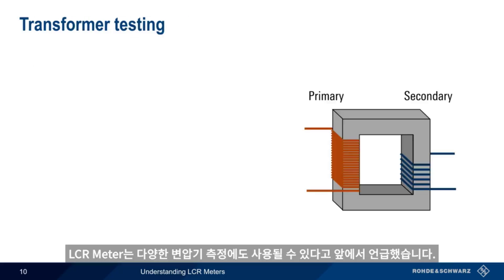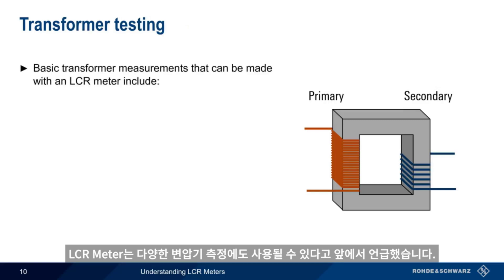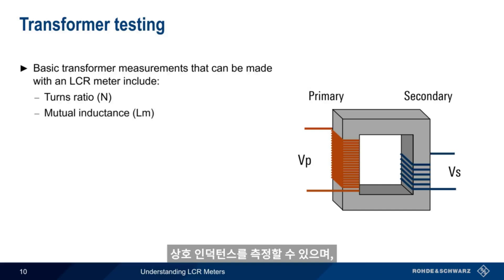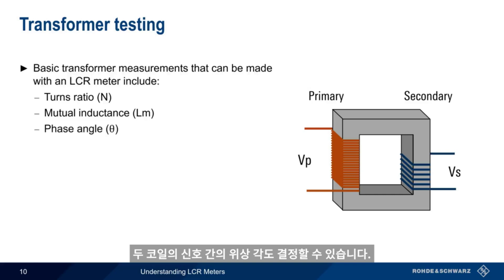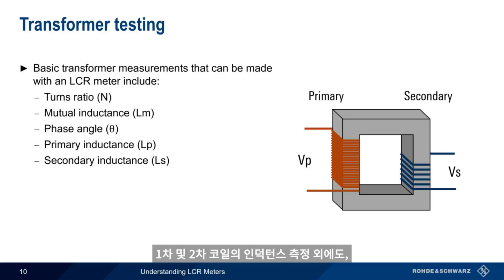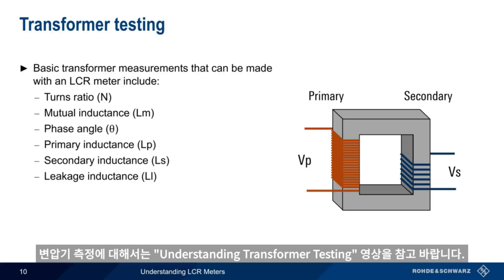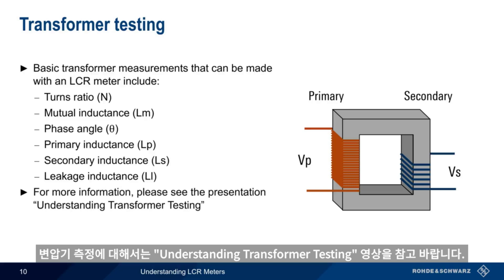LCR meters can also be used to make various transformer measurements. These include the turns ratio N, which can be calculated from the ratio of primary voltage to secondary voltage; mutual inductance, which is the change in voltage in one winding in response to a change in current in the other coil; and the phase angle between signals in the two coils. LCR meters can also find the leakage inductance, which quantifies the imperfect magnetic coupling between the two coils. Please see the separate presentation, Understanding Transformer Testing, for more details.